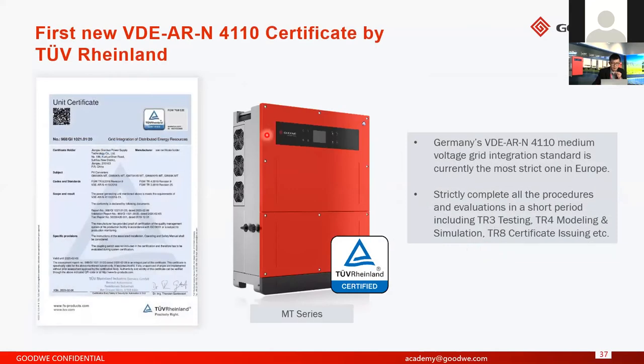Now this one is the 4110 certificate for our MT series. Actually, this certificate is very, very difficult to get. A lot of inverter manufacturers want to get this certificate because it is only for the German market. In the German market, if the system capacity is more than 135 kilowatt, your inverter must have this certificate. But this certificate is very difficult to get. But GoodWe MT series is the first inverter brand to get this certificate from TÜV.